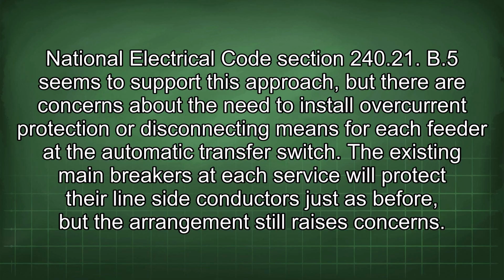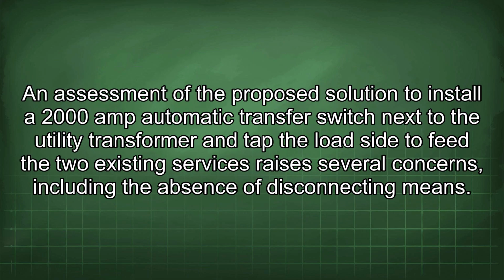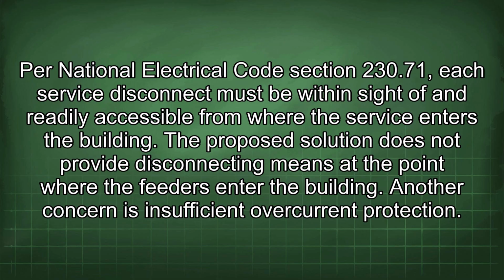The existing main breakers at each service will protect their line-side conductors just as before, but the arrangement still raises concerns. An assessment of the proposed solution to install a 2000 amp automatic transfer switch next to the utility transformer and tap the load side to feed the two existing services raises several concerns, including the absence of disconnecting means. Per National Electrical Code Section 230.71, each service disconnect must be within sight of and readily accessible from where the service enters the building. The proposed solution does not provide disconnecting means at the point where the feeders enter the building.